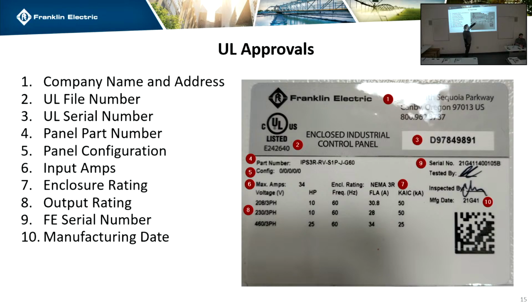Max amps is going to be the maximum on the input, and then all of your loads will be broken out. So if you have a panel, you can always see what load you need and what it's supposed to be to get to the 34 in this case. So these are not "and", it's "or". So this can do this one or this one or this one. And then we have a small jumper in there to change the voltage. So all you need to know is that the max amps is the input, and then all your load information is right here. The enclosure rating is going to be here.